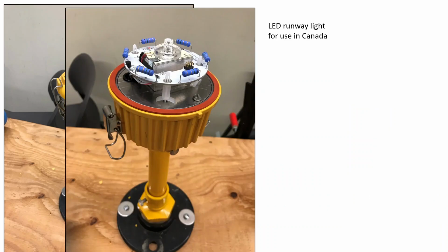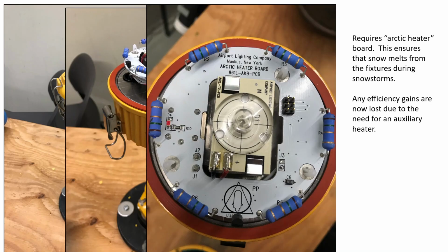And specifically for Canada and Northern Canada, we can see that there is the addition of a requirement to provide a little bit of heating. So if you look at the top of that board, there's some blue resistors, and those are being used as heaters. This particular system requires an Arctic heater board. This ensures that the snow melts from the fixtures during a snowstorm. Keep in mind, any efficiency gains are now lost due to the need for an auxiliary heater.